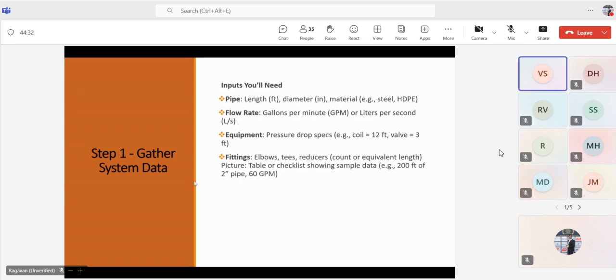Yes. Okay. Actually, before starting the pump head calculation, we have to gather all the essential data, including the pipe length, the diameter of the pipe, and what kind of material we are going to use. Usually we will use black steel, and carbon steel also. When it comes from underground, we will use HDPE pipe. Then determine the flow rate based on the cooling load calculation, identify the pressure drop of all the equipment along the longest path, and finally calculate the equivalent pipe length for the fittings and valves losses using the ASHRAE standard or the manufacturer data sheet.